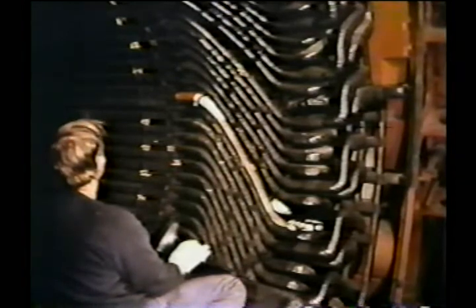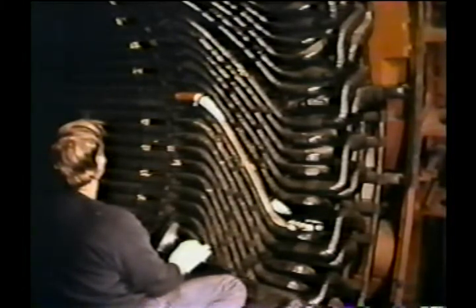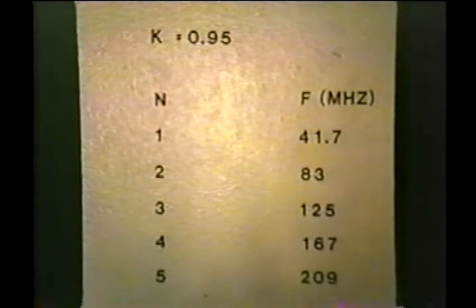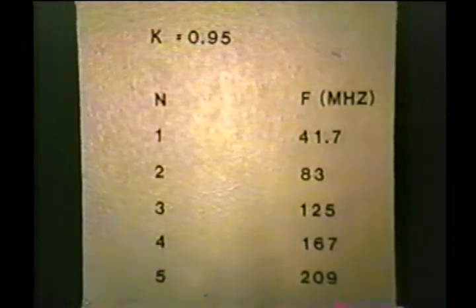Another obvious resonance circuit is in the end arms themselves, where they exit the iron, go out to a connection, and then come back to the iron again. You can use the same type of formulas with a velocity constant of approximately 0.95 and calculate again a series of frequencies that you might find there. This indeed is the case of the 41.7 megahertz. As you saw in the earlier curve, we did have a small bump at 42 megahertz.